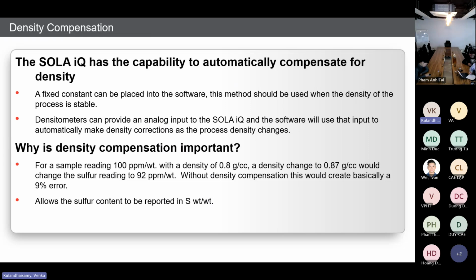If the process sample has a varying density throughout the day, then they have to use a separate density monitoring unit. Then the density output goes to our SOLA IQ as a live input. Based on the live input, our SOLA will calculate the process stream sulfur value on a weight per weight basis. So whenever the process density varies, the sulfur measurement level will also vary according to the density.